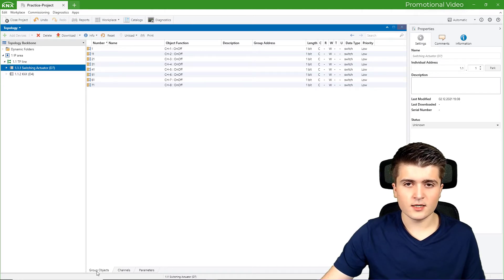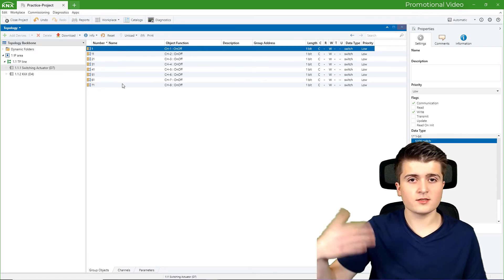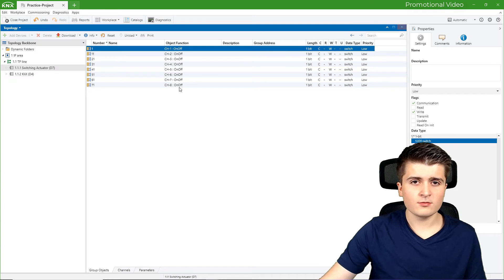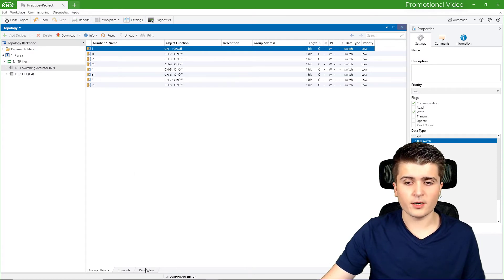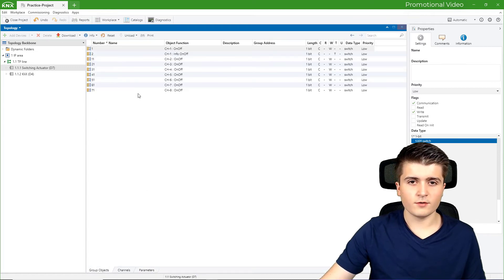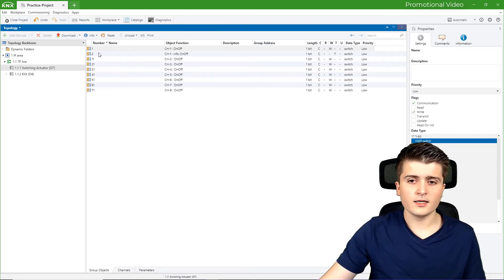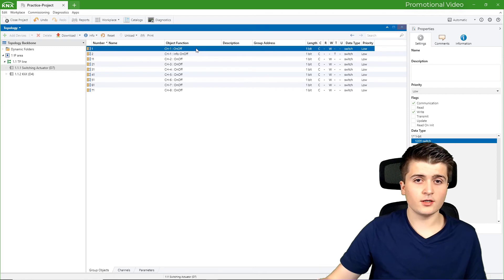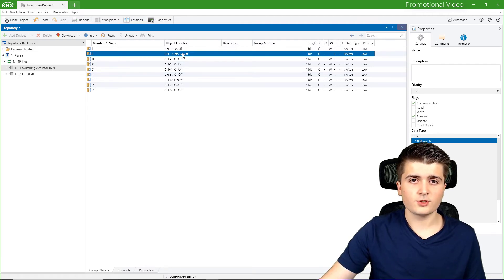I will mark the switching actuator and here you can see I have opened up the group objects. We have 8 group objects, and this simulated switching actuator consists of 8 different channels. By the description you can see that these group objects represent the function of switching on or off the corresponding channel — so channel 1 on or off. I can also enable additional group objects by going into the parameters of the device. For example, I can enable a feedback object, which gives us the information of the actuator — whether it was able to turn on its output channel or if it is broken. Now for the first channel I have 2 group objects: the on/off object to turn the channel on and off, and the info feedback object. So these are the functions of the device which we get as group objects.